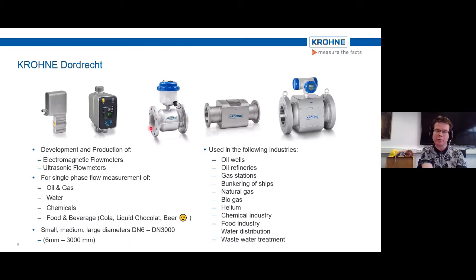That will limit the amount of liquid or gas you can pump through it. So that's why there cannot be any obstruction inside the pipe, it just needs to be a straight pipe. All the equipment to measure the flow has to be put around the pipe. There's a big coil put around it, from where you introduce an electromagnetic field to measure the flow speed. So, does that answer your question, Garrett?